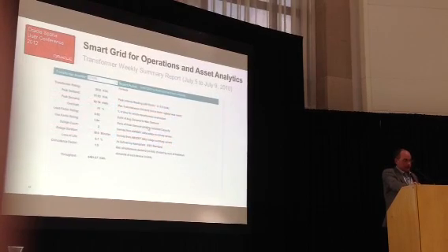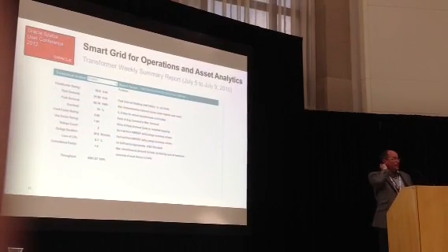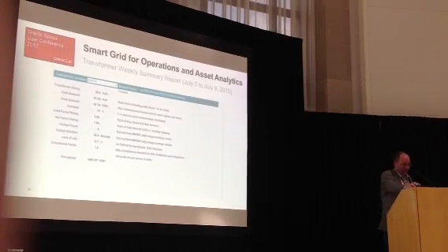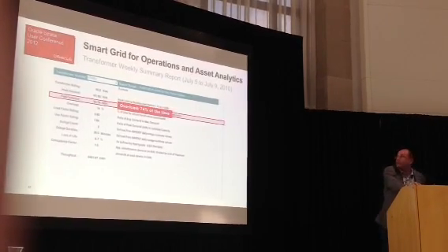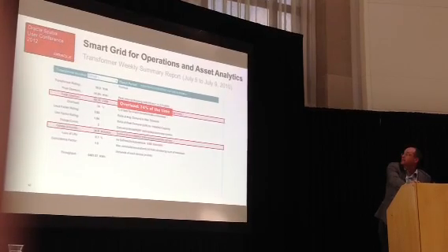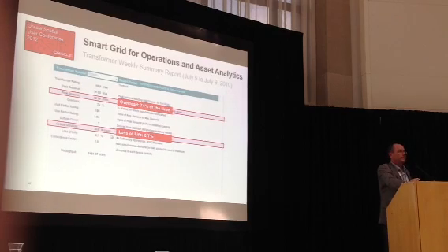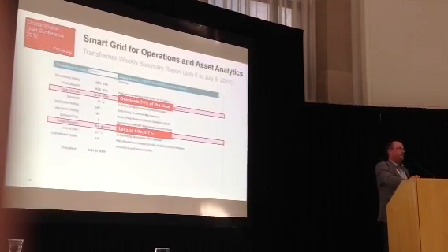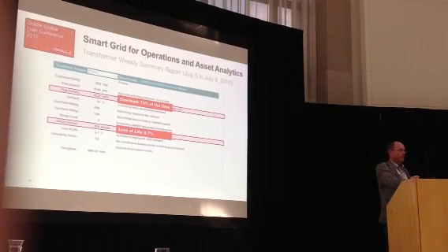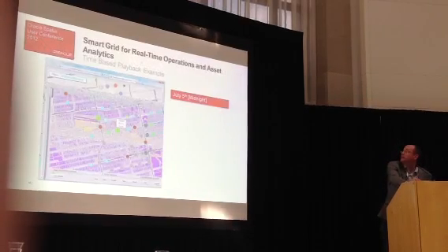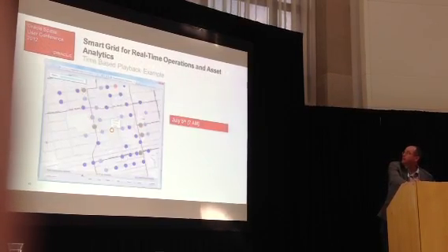What's interesting is if you don't let that transformer cool down, and we'll look at a week now, it's kind of exponential how you lose the life on a transformer. So in this case, it's overloaded 74% of the time, and it lost 6.7% of its life in a week. They're supposed to last 50 years. They're not supposed to lose close to 10% of their life in a single week. So you can see where they get concerned about outages and equipment. And they're expensive to change. I don't know what a transformer costs to change, but a lot of money. So helping to reduce that. And of course the playback, which we're showing.